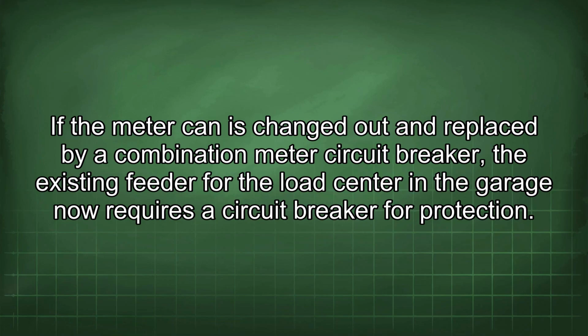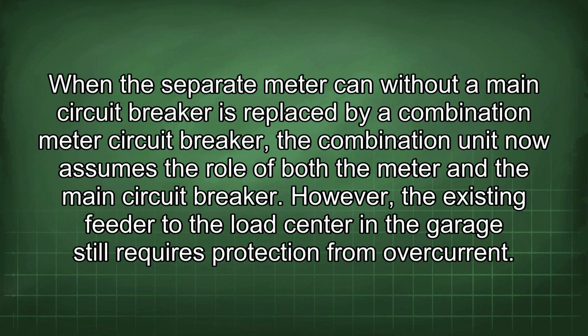The meter can is changed out and replaced by a combination meter circuit breaker. The existing feeder for the load center in the garage now requires a circuit breaker for protection. When the separate meter can without the main circuit breaker is replaced by a combination meter circuit breaker, the combination unit now assumes the role of both the meter and the main circuit breaker. However, the existing feeder to the load center in the garage still requires protection from overcurrent.